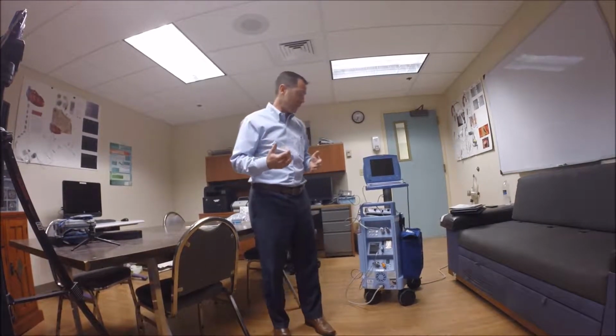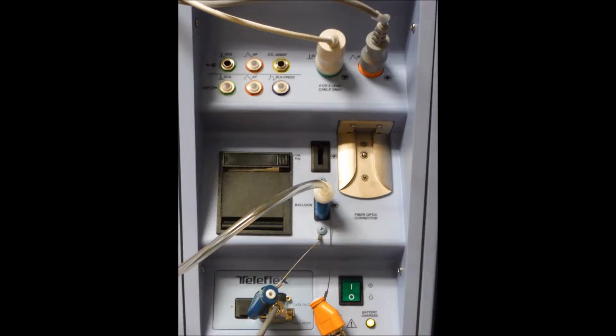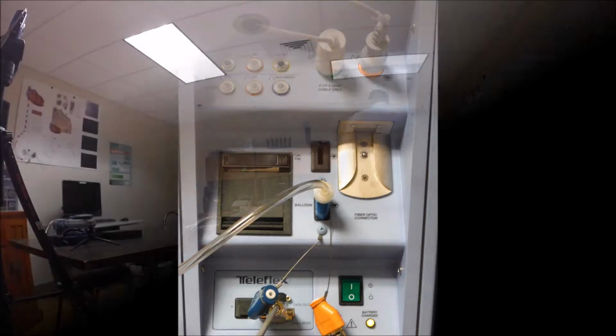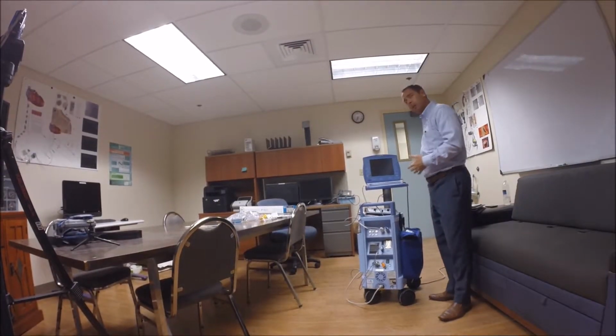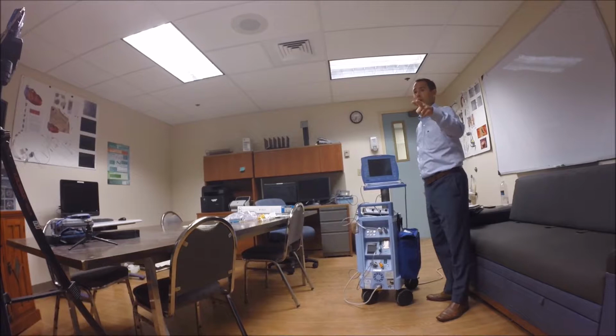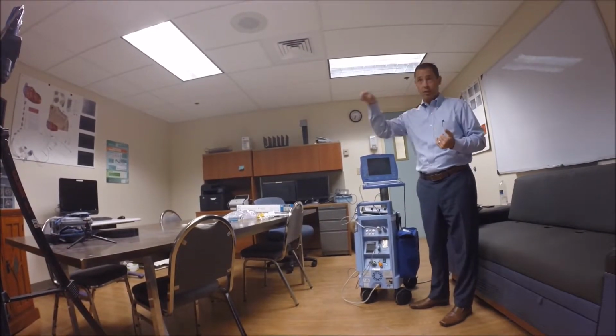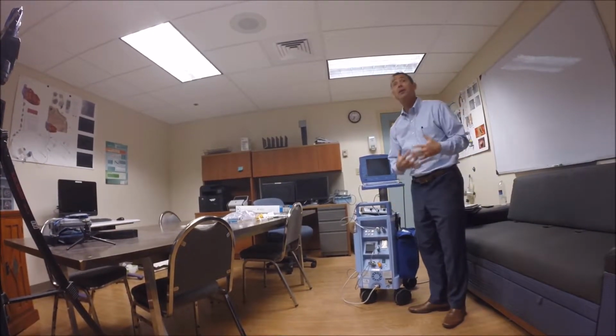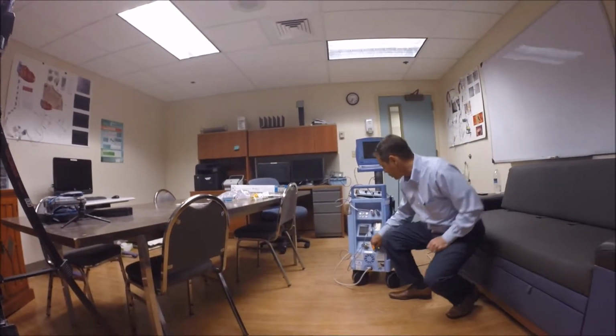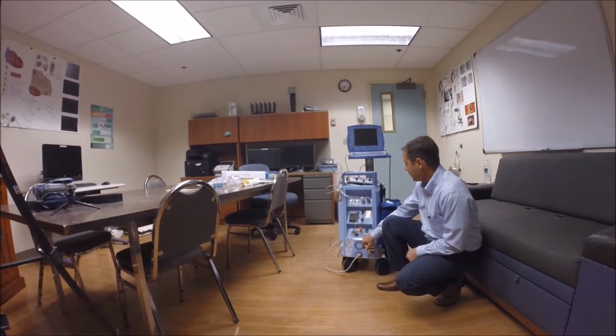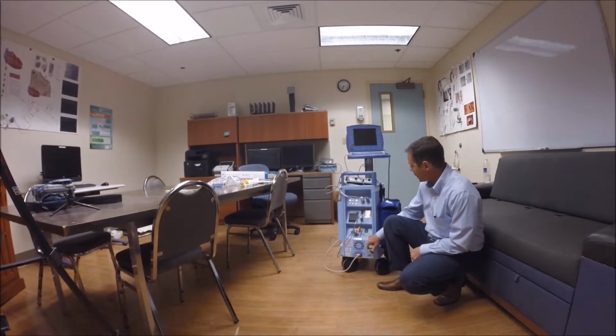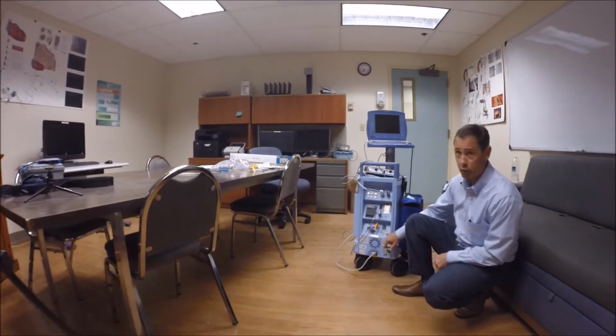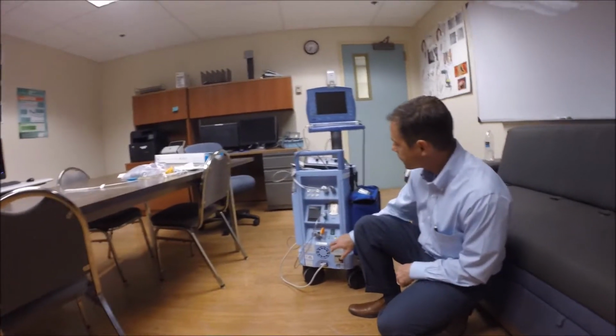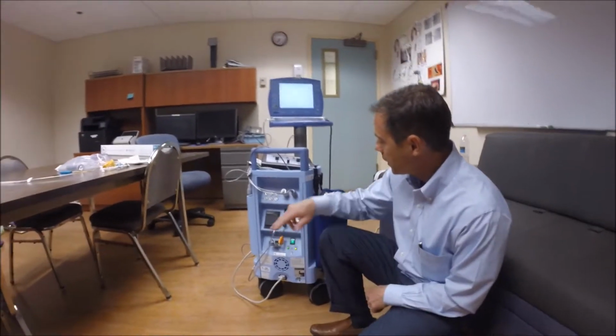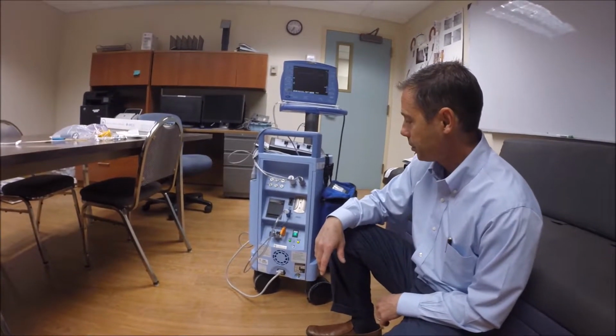All right, so let's get into the ease of use now. We make sure that the pump is always plugged in 24/7 inside of your transport vehicles into your inverter. We have a battery. Your battery is a 90-minute battery. Down here you'll notice that the green light indicates that it is plugged in, and the yellow light indicates the battery is fully charged at 80% or higher. Here is my main power switch powering on the pump.